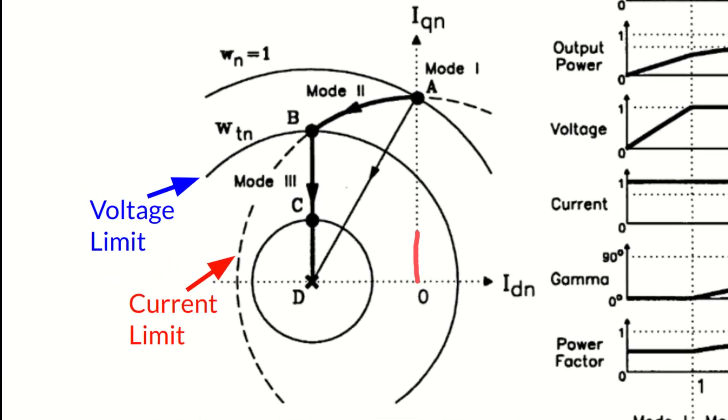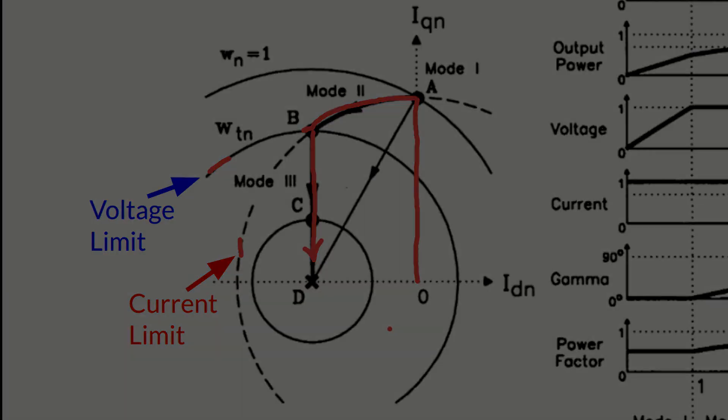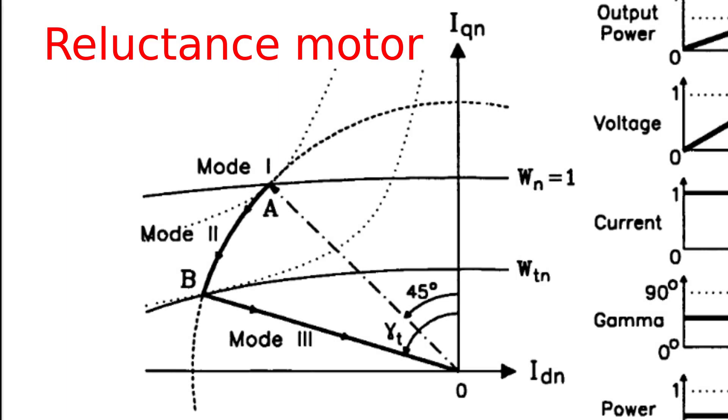We pass initially from MTPA, or maximum torque per ampere, to field weakening, and then once we reach the limit of both the stator current and the supply voltage, we start the MTPV, or maximum torque per voltage method, which requires the lowering of the stator current vector along a specific path to allow for the peak torque at those increasing speeds. And this path depends on the motor type and design.